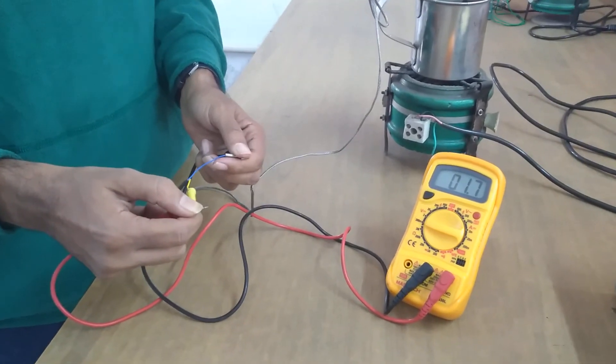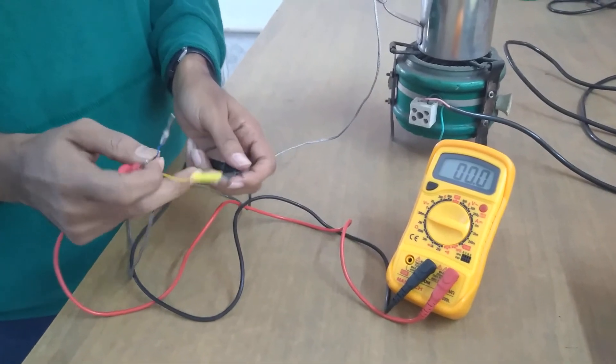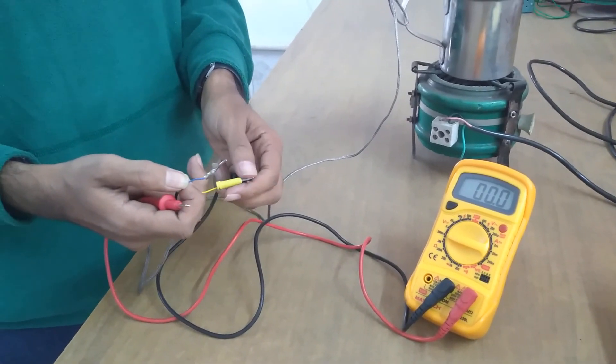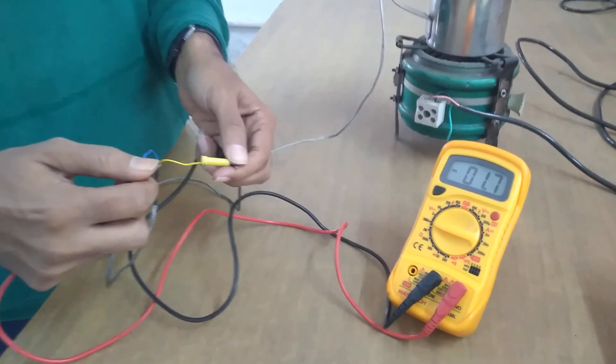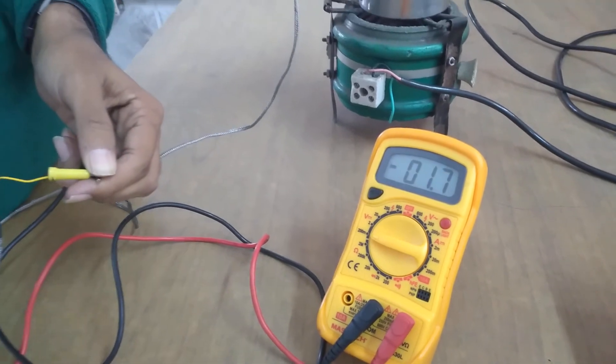Now we are going to demonstrate the polarity issue. So you can see that red to yellow and black to blue shows around 1.7 millivolts. Now if I flip the terminals, that means yellow to black and blue to red, you will find that the polarity also flips. This is minus 1.7 millivolts.